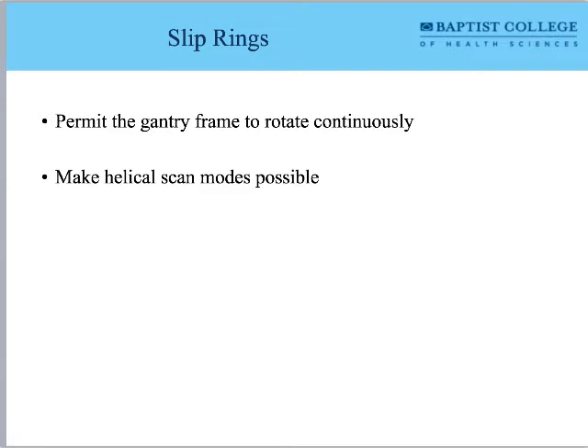Slip rings allow this thing to spin around and make helical scan modes possible. If axial mode is like getting bread slices, helical scanning is like the honey-baked spiral cut. Because it can spin continuously, we can also move the table through continuously and get this spiral slice. We need slip rings for that.